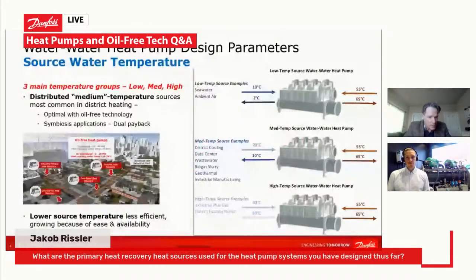I've got a couple slides for that as well, so the primary heat recovery heat sources that we've utilized for these systems - I covered this earlier, but I'll show a few examples. There's an important story behind what drives our focus on these specific applications. As I mentioned earlier, every 1K that you can decrease the differential of work that the heat pump has to do equals about 1.5% efficiency improvement. That pushes you toward focusing on higher temperature heat recovery heat sources.